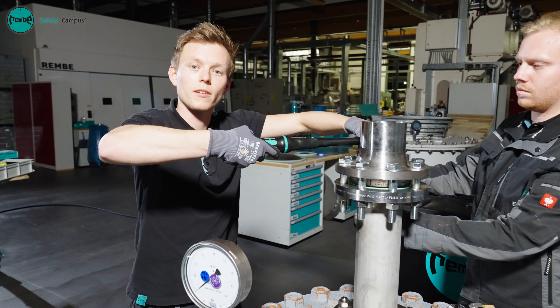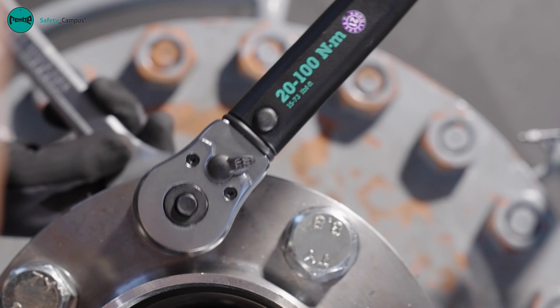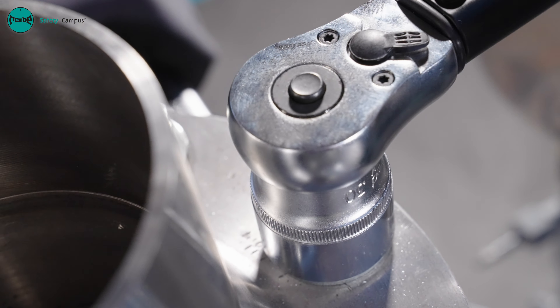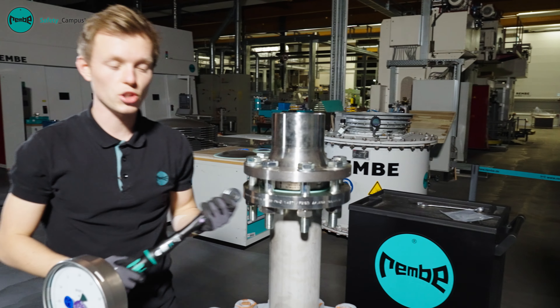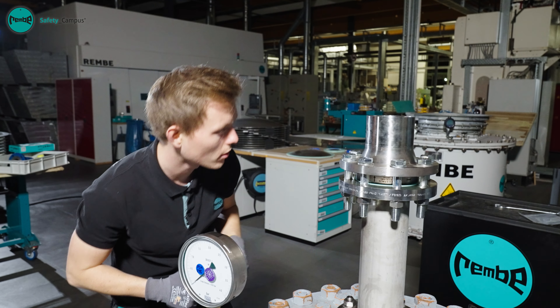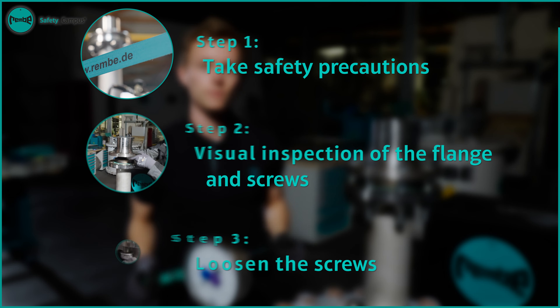It is important to tighten the rupture disc in three steps. Tightening across prevents the rupture disc from tilting during tightening. To finish, the rupture disc and bolts should be checked thoroughly once again. If no damage is found here, the plant can be started up.